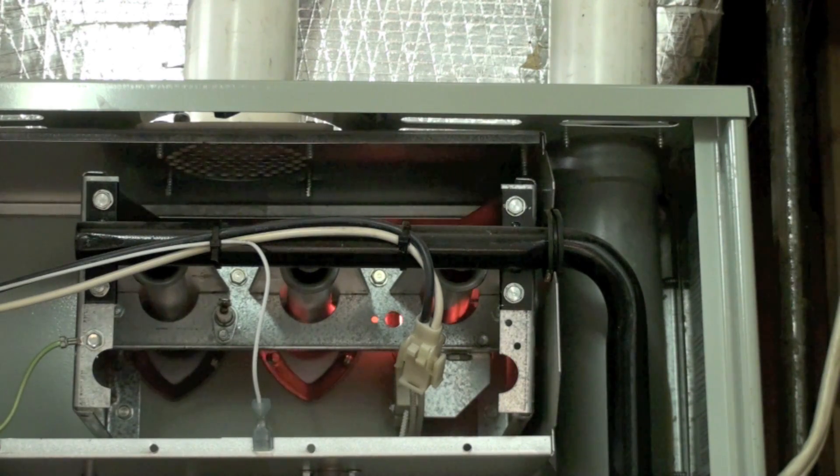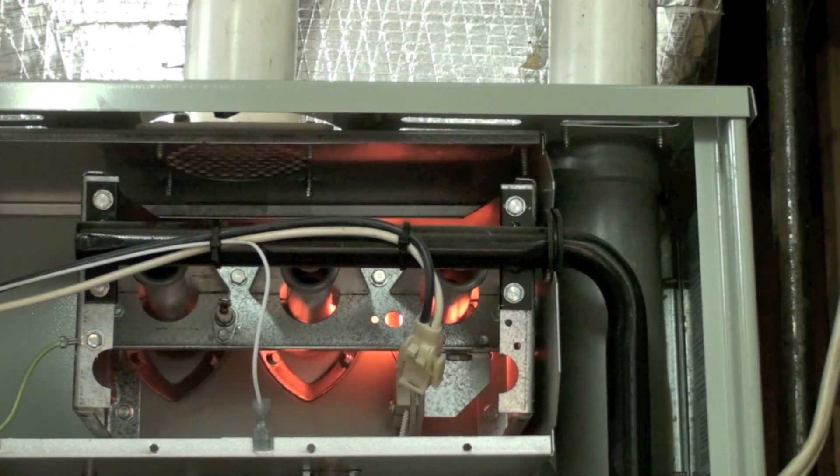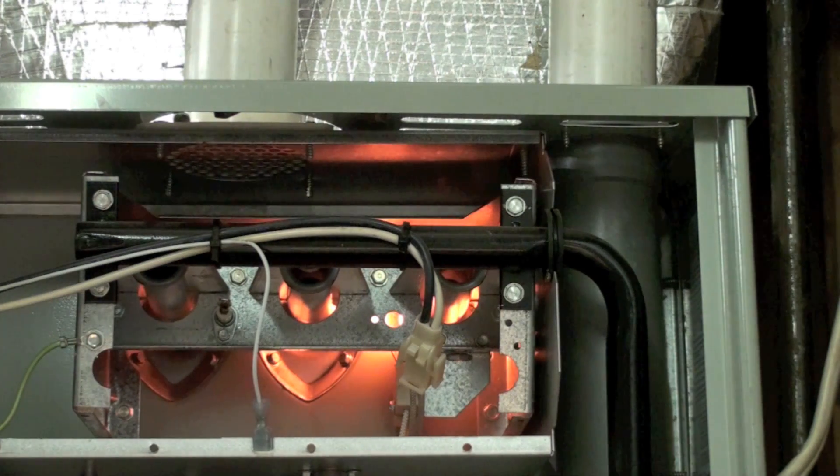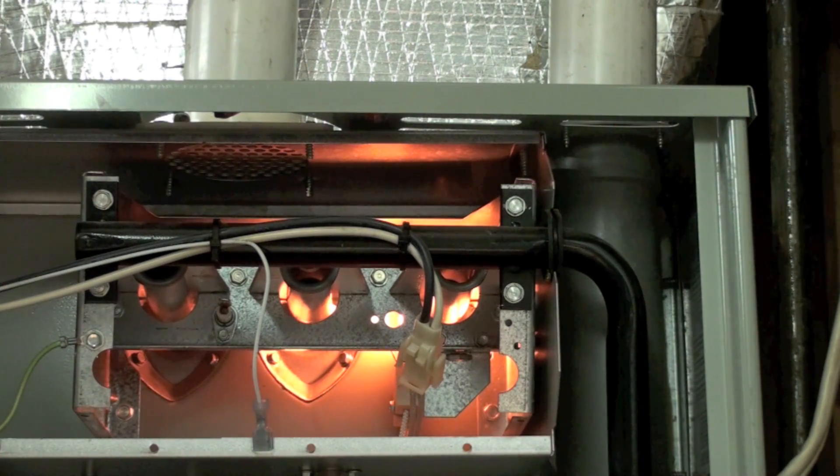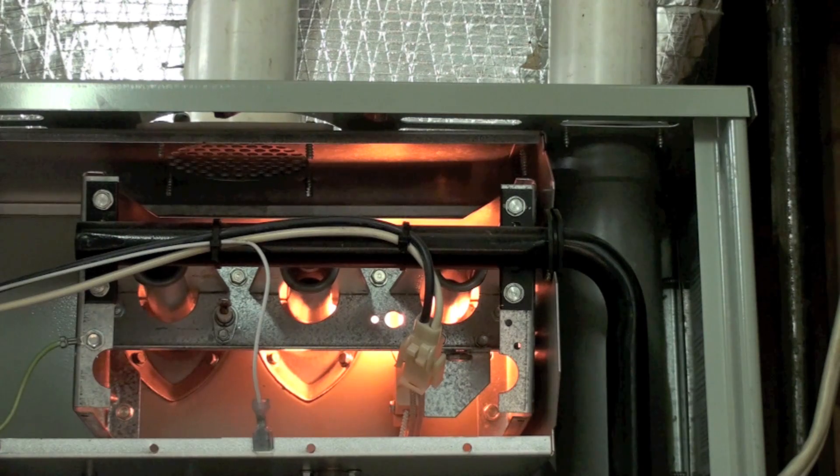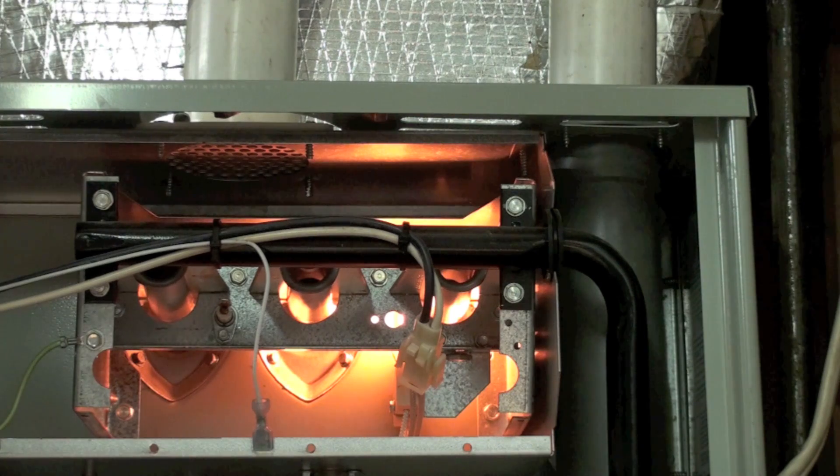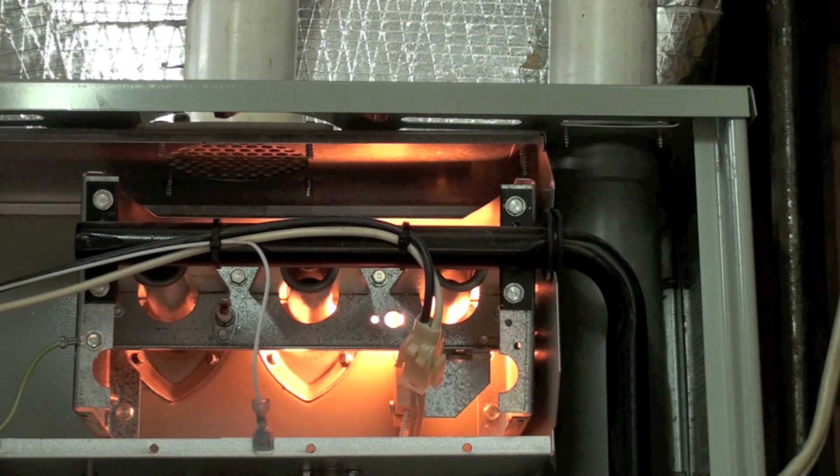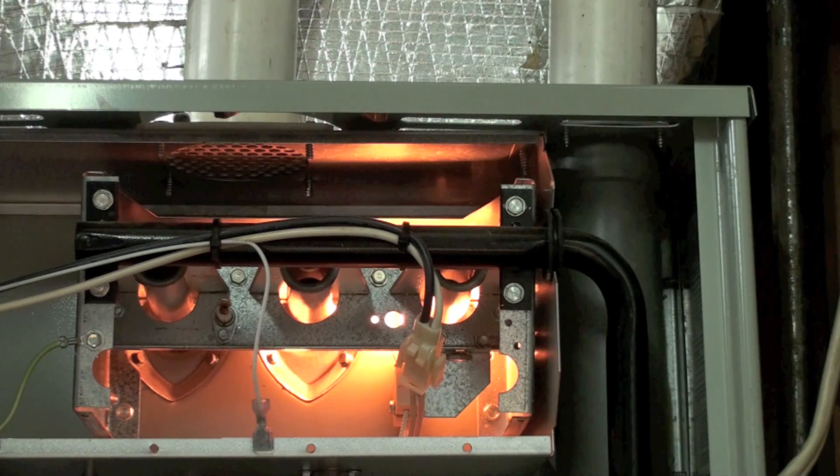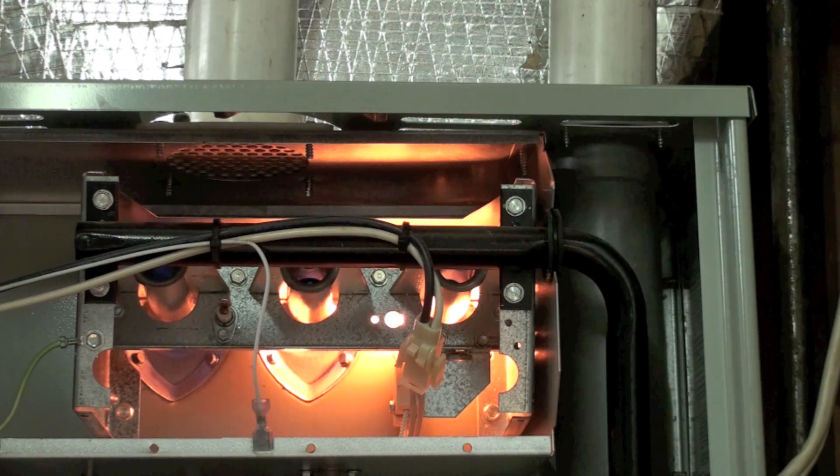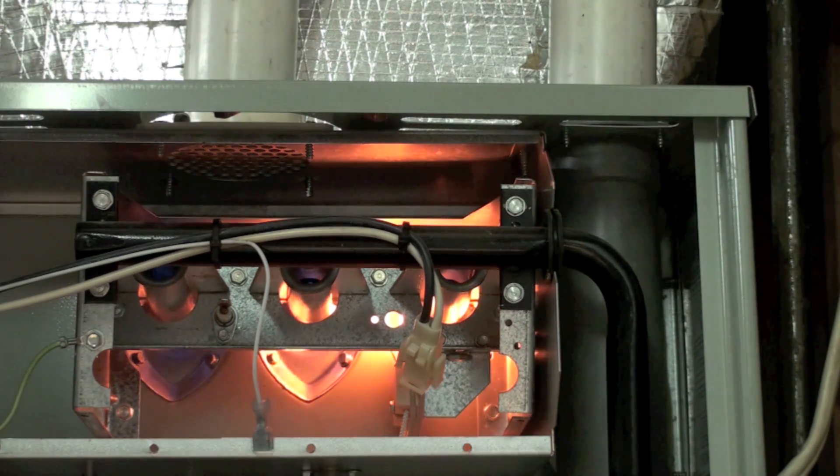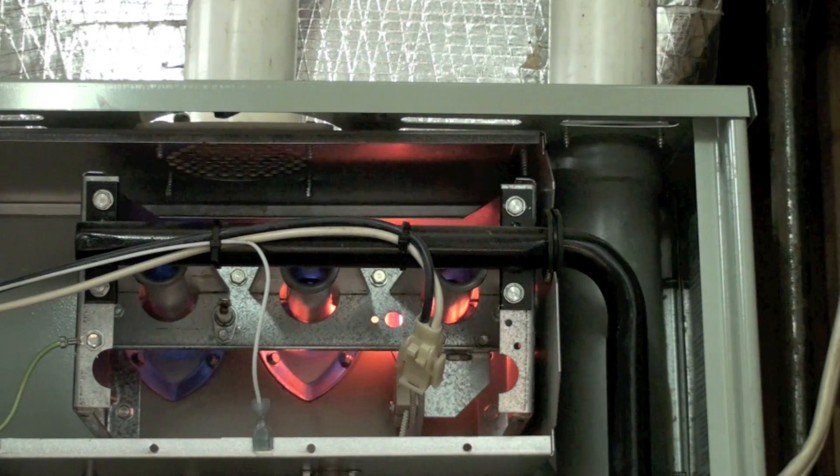Okay, hot surface igniter is back on. Burners have lit, that means gas valve is open. We're not going to sense flame so it's going to shut down.